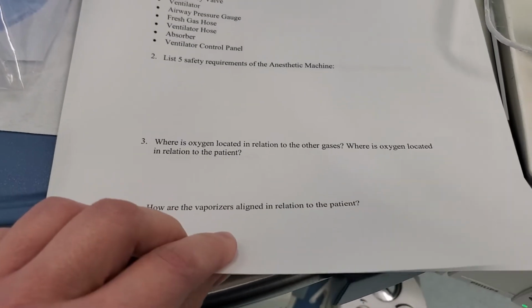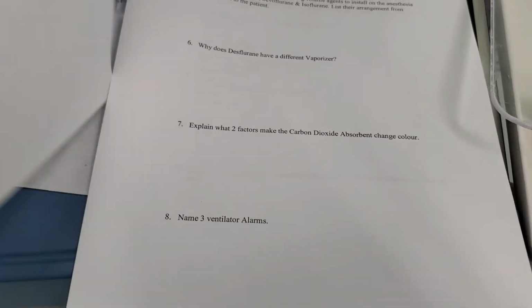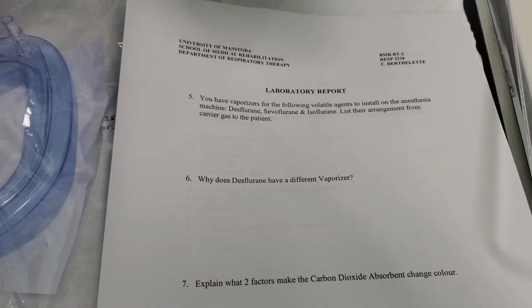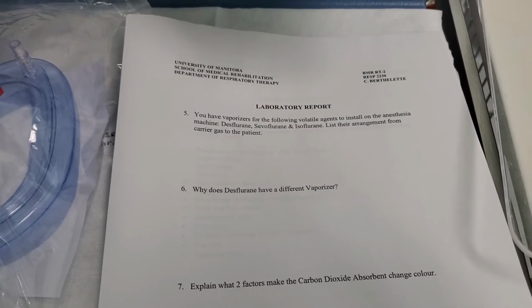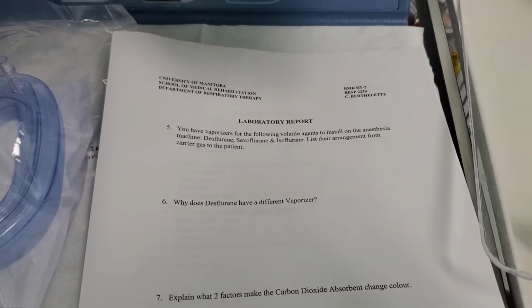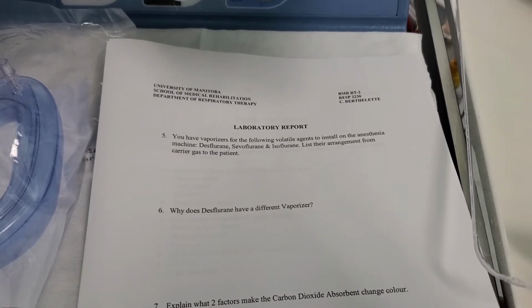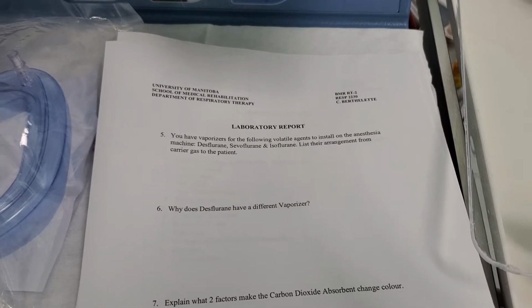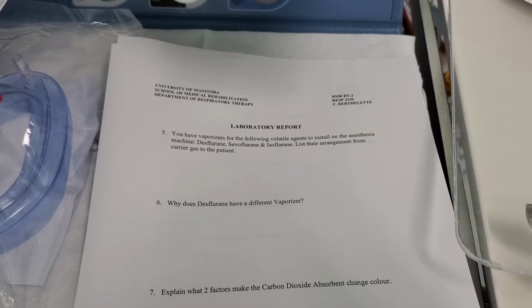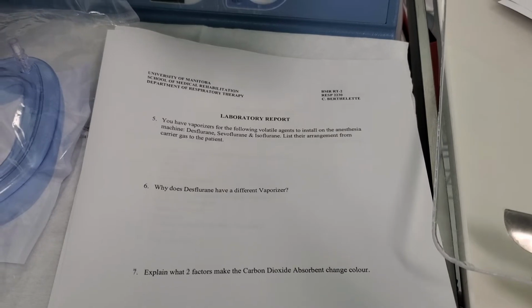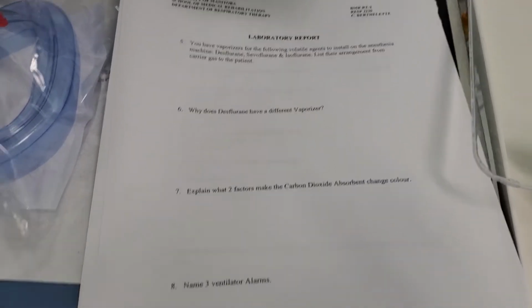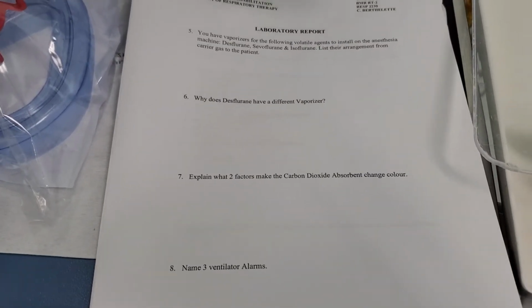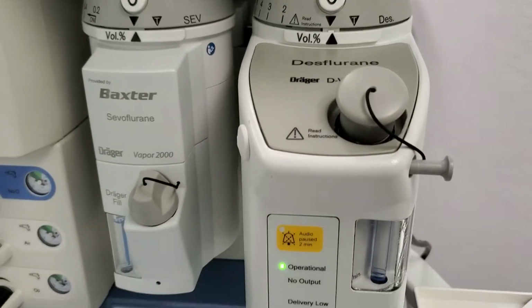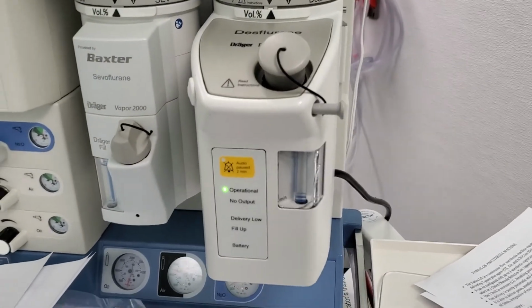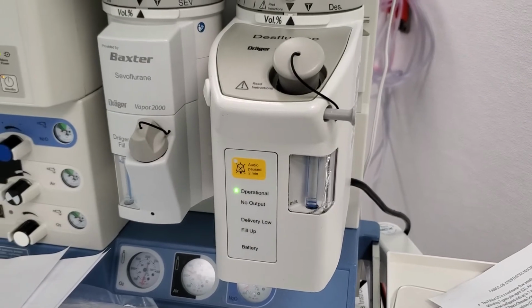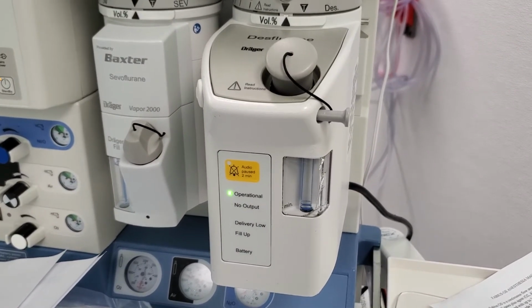So how are the vaporizers aligned? The most potent must be closest to the patient. So basically, if you think about your MAC values of the different gases, you'll be able to sort out which one is more potent of the three and closest, and then the second most potent, and then the third most potent. So you guys can answer that. Also in the notes, desflurane does have a different vaporizer. Basically, we heat it to maintain a constant temperature. It's heated to 39 degrees Celsius and pressurized to 2 atmospheres.